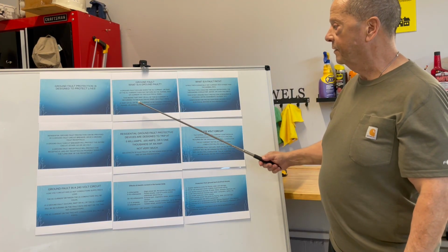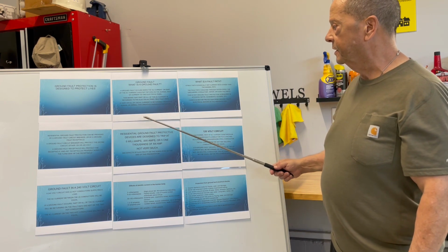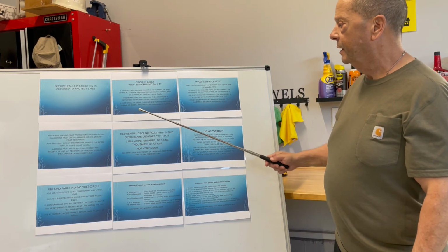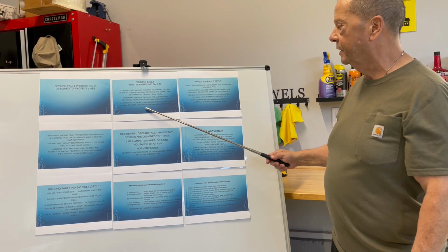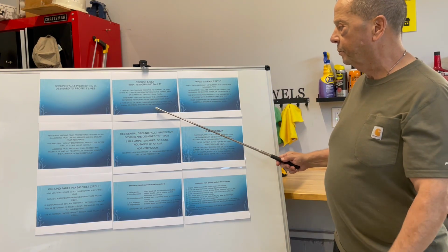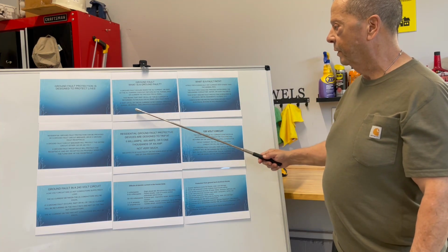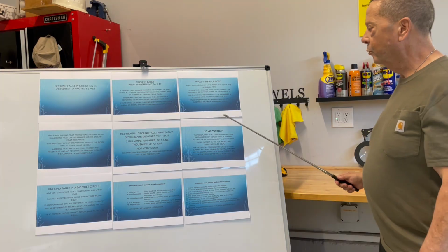A ground fault occurs when the AC current, or part of the AC current, does not return on the normal path of current to the electrical panel. This means that part or all of the AC current is returning to the electrical panel on a fault path. If part or all of the AC current is returning through a human or an animal, this creates a hazardous situation. What is a fault path?